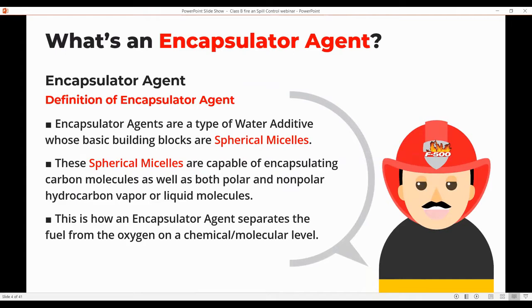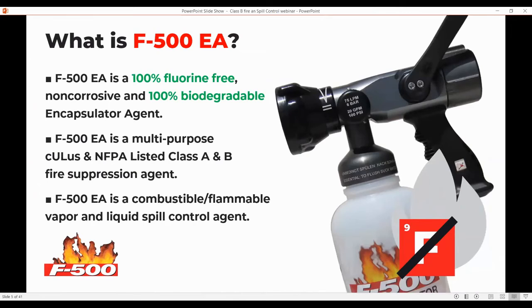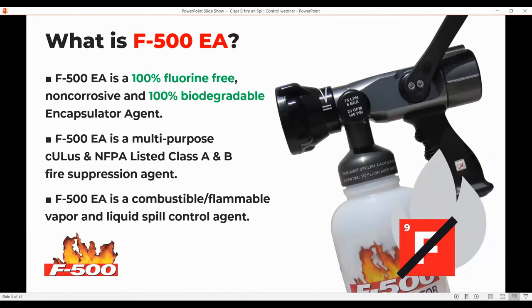Those spherical micelles are capable of encapsulating carbon molecules, as well as both polar and nonpolar hydrocarbon vapors in both the liquid and vapor state — so it can do it either way. Those micelles encapsulate that fuel on a molecular level, separating the fuel from the oxygen. The particular encapsulating agent we're going to be talking about today is F500. It is 100% fluorine free, non-corrosive, and 100% biodegradable.